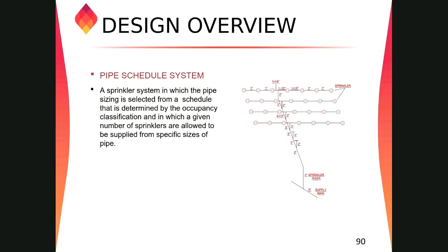So this is the most remote location. They will consider these sprinklers as 1, 2, 3, 4, 5, 6, 7, 8, 9, and then 10, 11, 12, 13, 14, 15, 16, and so on. The last one will be the last node. Like this we have to do in the Elite software. So number 1 is the most remote location in the Elite software.